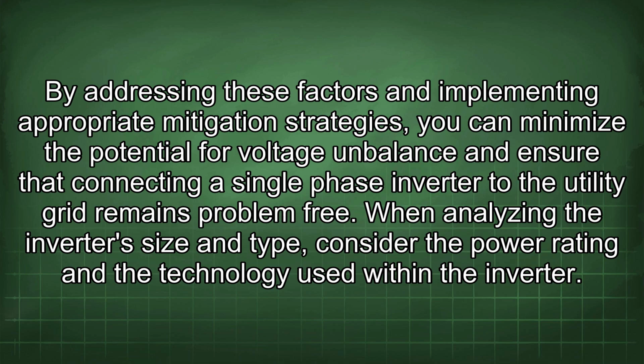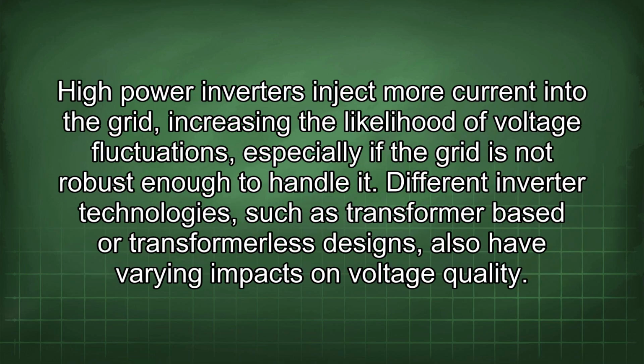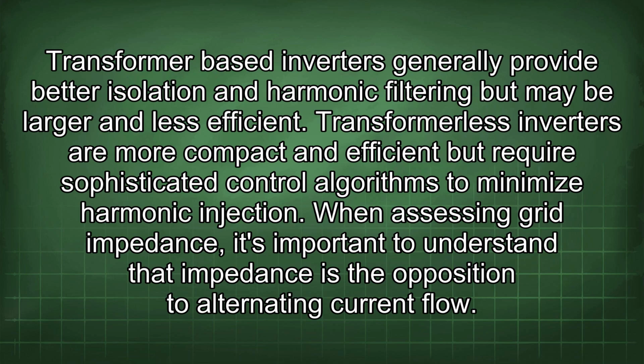When analyzing the inverter's size and type, consider the power rating and the technology used within the inverter. High-power inverters inject more current into the grid, increasing the likelihood of voltage fluctuations, especially if the grid is not robust enough to handle it. Different inverter technologies, such as transformer-based or transformerless designs, also have varying impacts on voltage quality. Transformer-based inverters generally provide better isolation and harmonic filtering but may be larger and less efficient. Transformerless inverters are more compact and efficient but require sophisticated control algorithms to minimize harmonic injection.